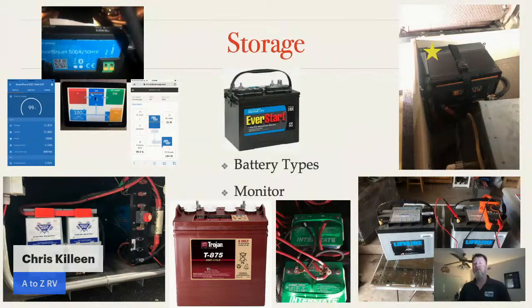You may have heard the misnomer that every time you go below 50%, you damage your battery. In reality, every time you run a cycle in a battery, regardless of type, the manufacturer has a table specifying how many cycles you'll get out of it. For lead acid and AGM, if you run cycles of 20 to 30% and rarely go below 50%, you'll prolong the life. A lead acid battery can easily achieve 5 years if you take care of it, keep the water above the cells, and don't repeatedly discharge below 50%. AGMs are similar but can get out to 8 years, especially if well taken care of.